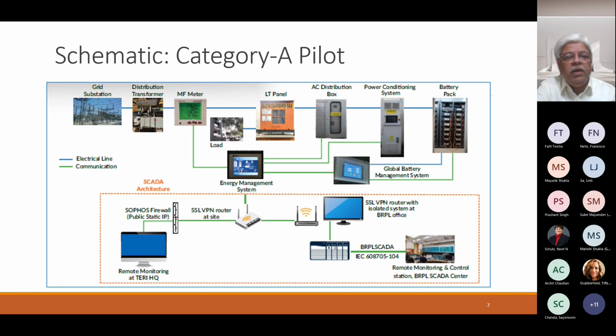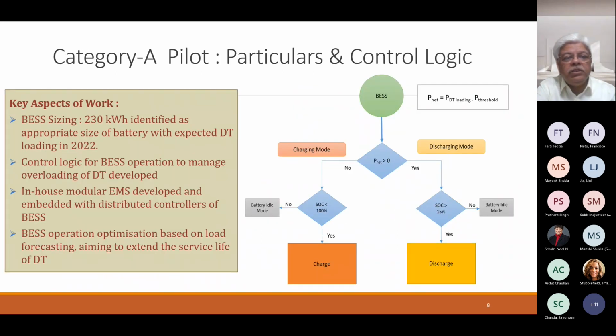In the next slide, we look at the control logic. The battery, about 230 kilowatt hour, was identified as the best possible or appropriate size given the expected loading on the DT. The logic shown on the right-hand side assumes, for practical purposes, a DT loading of 990 kVA.